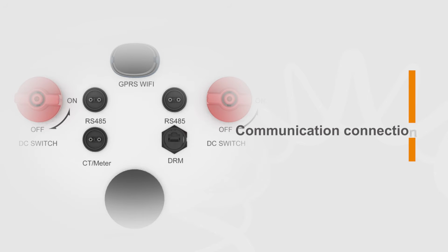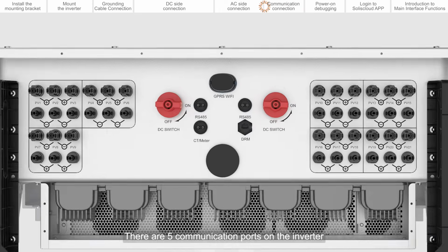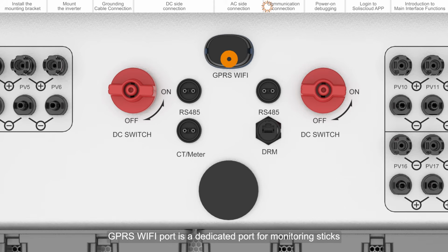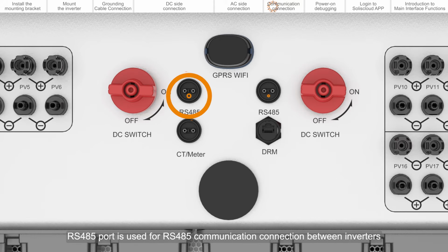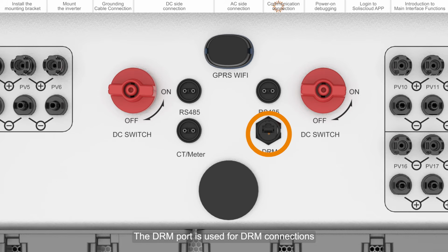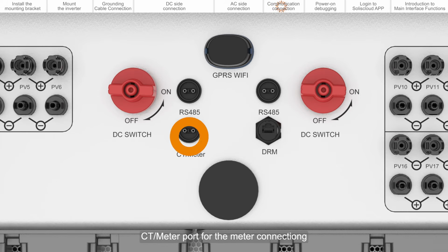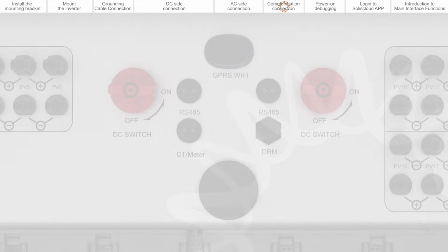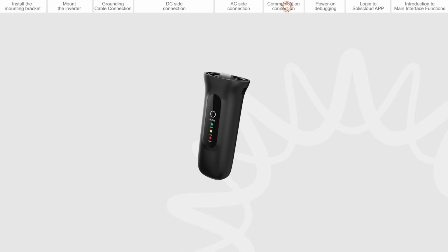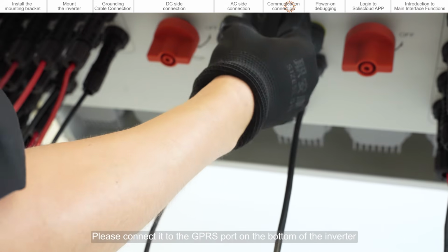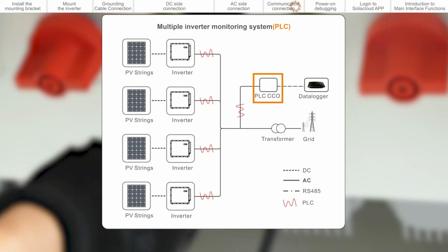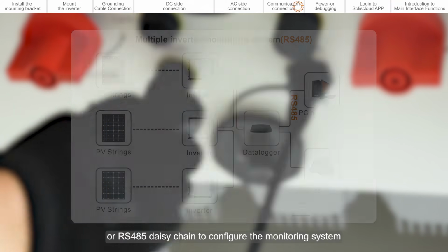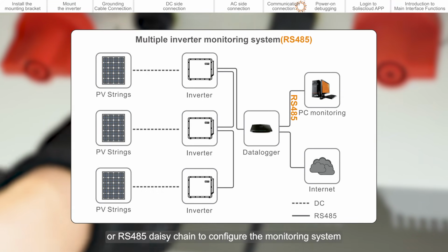Communication connection. There are 5 communication ports on the inverter. GPRS Wi-Fi port is a dedicated port for monitoring sticks. Our RS485 port is used for RS485 communication connection between inverters. The DRM port is used for DRM connections. CT, meter port for the meter connection. If you choose Solis Data Logger, please connect it to the GPRS port on the bottom of the inverter. You can also choose PLC method or our RS485 daisy chain to configure the monitoring system.